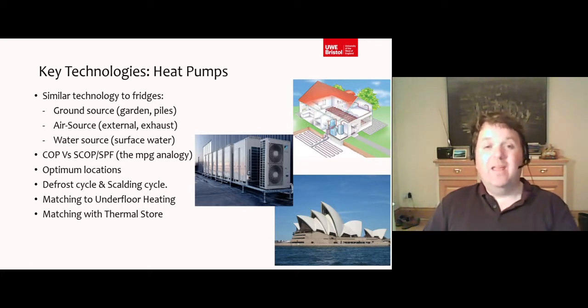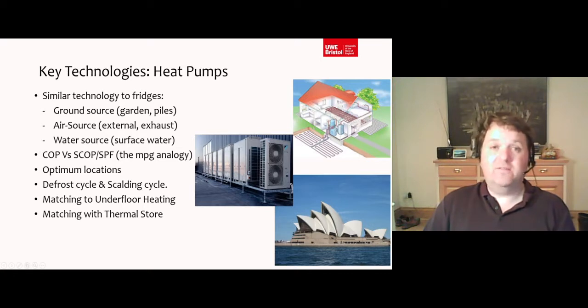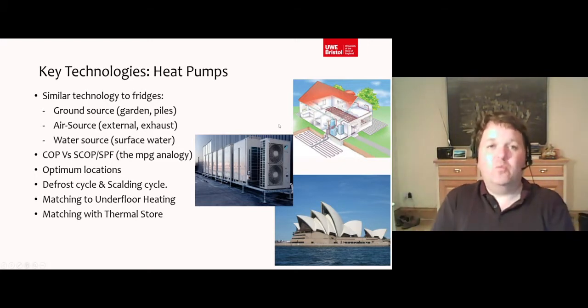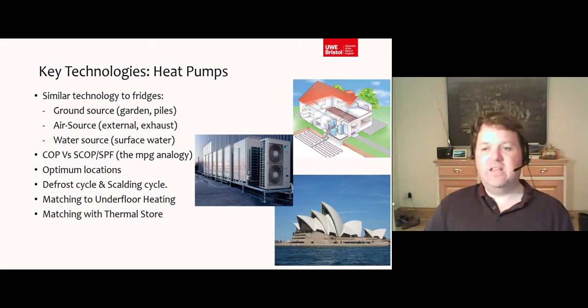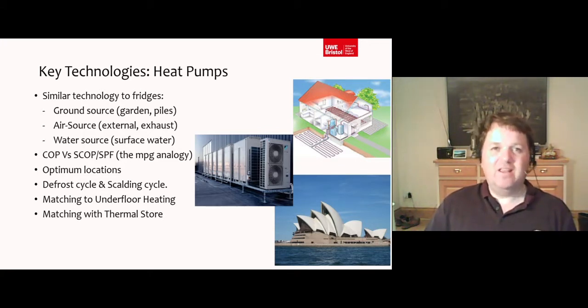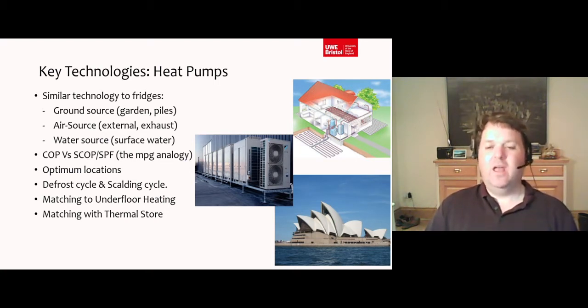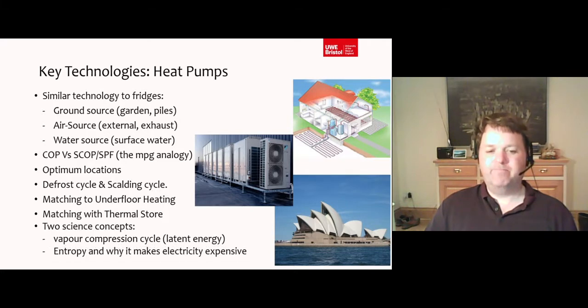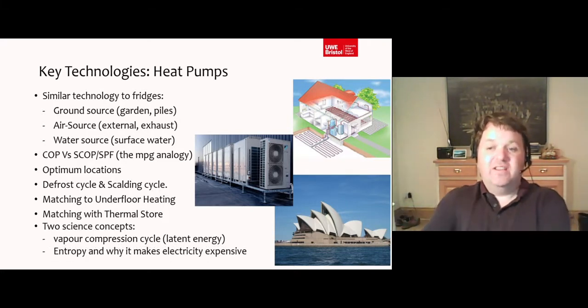Heat pumps are also a good match with a thermal store. Because you're using electricity, you can get cheaper rates at night time and charge a thermal store overnight, then use that store during the day. That store might be the heavy thermal mass of your building's walls and structure, or it might be a dedicated mechanical drum with a phase change material that you charge at night and which delivers heat during the day. You can also incorporate something like weather compensation to predict whether you need a full charge or can get away with half a charge for the next day, so you're using less electricity.